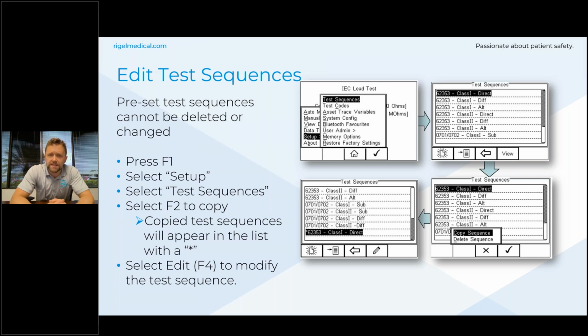Now, in most cases, this isn't going to be a requirement. The default sequences are built there based on the standards. For instance, if you've got NFPA 99 class 1, that's already pre-programmed with all the test limits and the processes for carrying out that test.